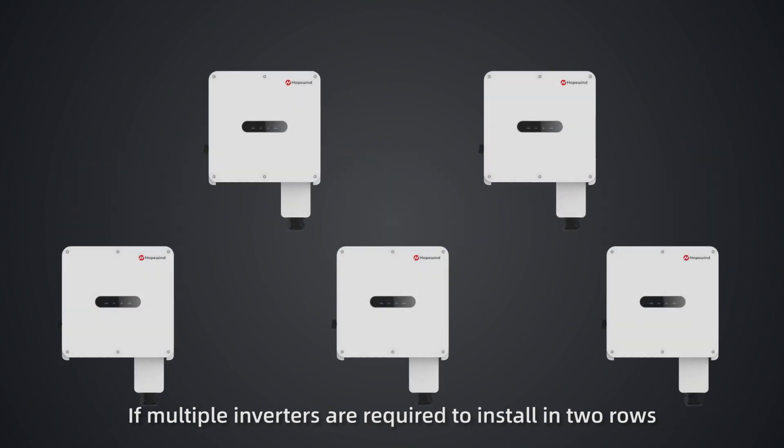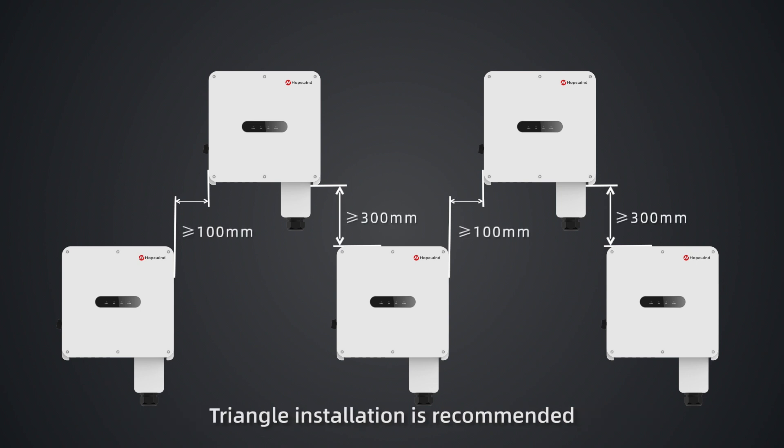If multiple inverters are required to install in two rows, triangle installation is recommended. More than 300mm space should be reserved between the two rows and more than 100mm space should be reserved on the left and right of the inverter.